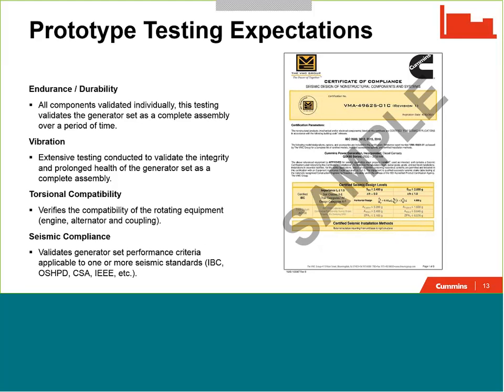A manufacturer will be conducting this torsional compatibility analysis to ensure the product is fully developed as a complete assembly, whereas an assembler may be just taking these components, piecing them together, and shipping them out the door. The last one I'll talk about here, and this is one of our potentially destructive tests, is seismic compliance. You see this in various flavors that are needed based on the regions. This may be IBC or OSHPD, CSA, IEEE. What you should see from any generator set vendor is a document that looks like the sample on the right-hand side of the screen that indicates compliance with the particular standard to the level of performance that you need.